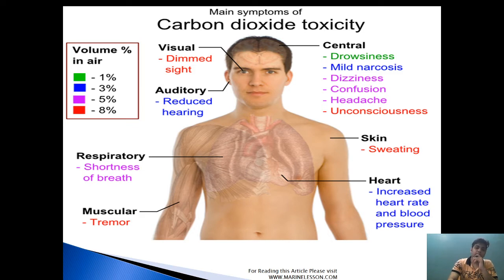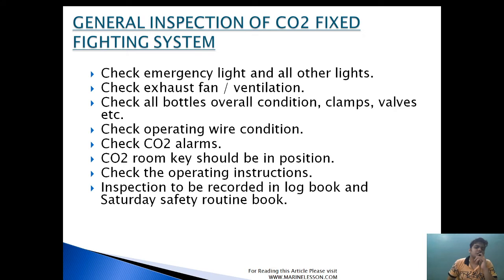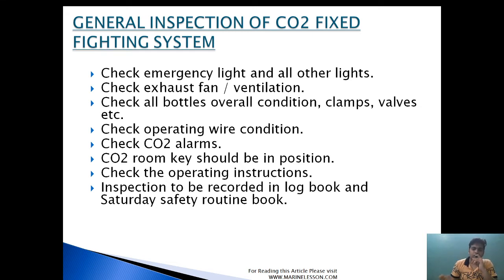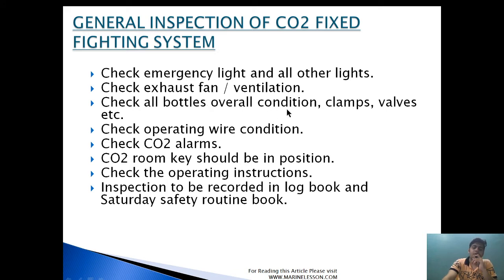For normal inspection of the CO2 room, you should check the emergency light and all other lights fitted in the CO2 room to ensure they are working. Check the exhaust fan and ventilation — the CO2 suction in the exhaust fan should be from the bottom, and it should perform six air changes in a particular time period. Check all bottle overall condition, clamp valves — carry out visual inspection — and check the operating wire condition for any wire breakage or stranding.